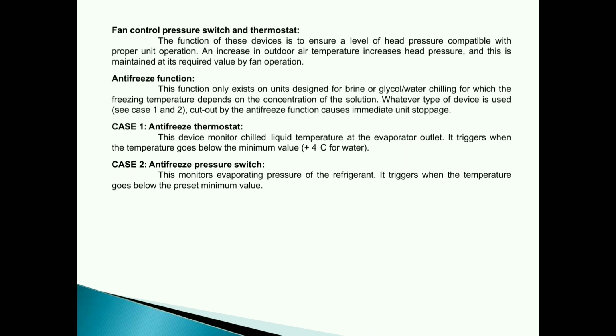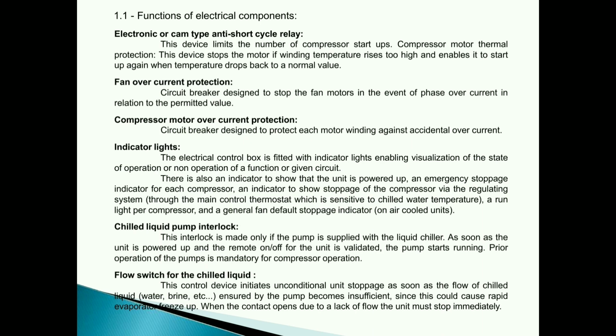This device monitors chilled liquid temperature at the evaporator outlet. It triggers when the temperature goes below the minimum value, plus 4C for water. Case 2, antifreeze pressure switch. This monitors evaporating pressure of the refrigerant. It triggers when the temperature goes below the preset minimum value.